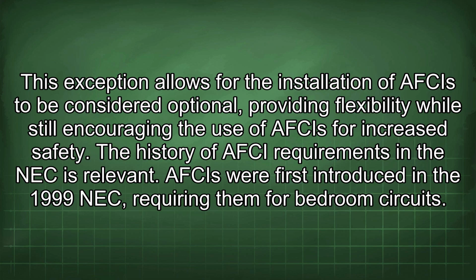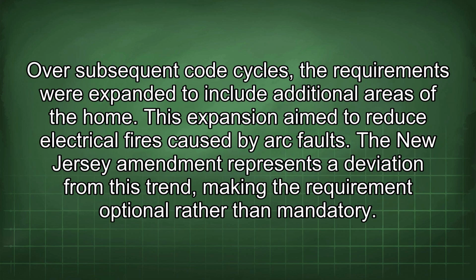The history of AFCI requirements in the NEC is relevant. AFCIs were first introduced in the 1999 NEC, requiring them for bedroom circuits. Over subsequent code cycles, the requirements were expanded to include additional areas of the home. This expansion aimed to reduce electrical fires caused by arc faults. The New Jersey Amendment represents a deviation from this trend, making the requirement optional rather than mandatory.